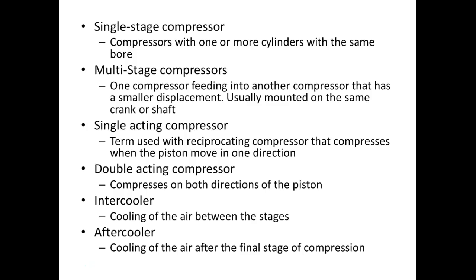Single stage compressor, these are compressors with one or more cylinders with the same bore. Multi-stage compressors, one compressor feeding into another compressor that has a smaller displacement. These two compressors are usually mounted on the same crankshaft. A single acting compressor, these are terms used with reciprocating compressors that compress when the piston moves in one direction. Double acting compressors, these compress in both directions of the piston.